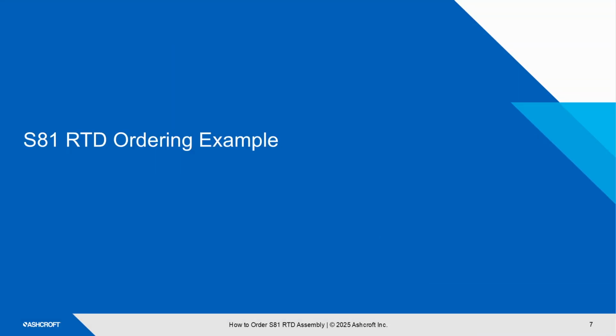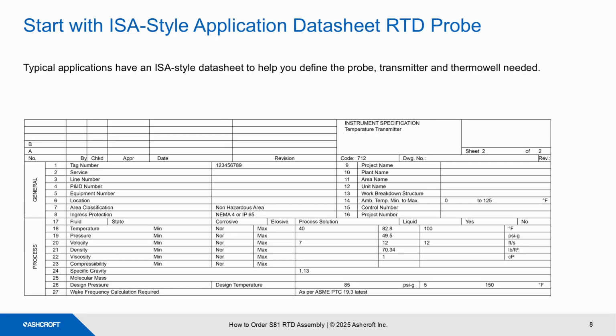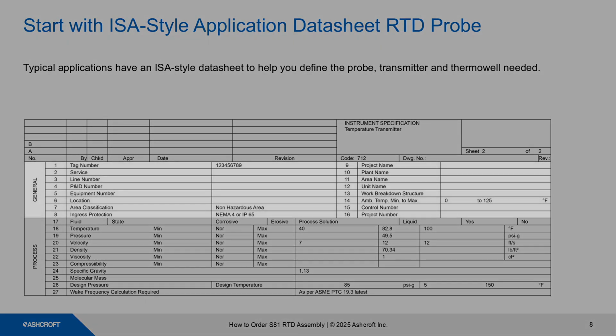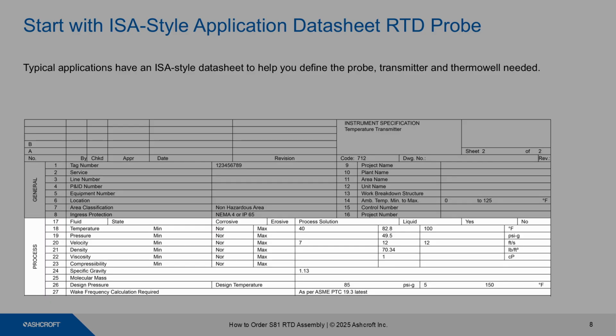Okay, Dave, now that we know the ordering requirements, can you show us how to build the actual part numbers for these products? Yes, we will use an ISA-style data sheet, which describes the application to define the probe, transmitter, and thermowell needed. So we're going to look at the general section first for the requirements of the area classification. This is a non-hazardous area requirement. Then we're going to look at the process section, and we're going to look at the temperature and pressure ratings just to make sure there isn't anything of concern.